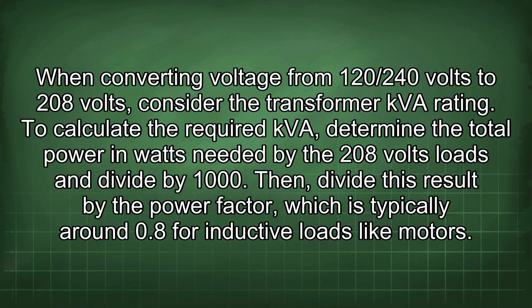When converting voltage from 120/240 volts to 208 volts, consider the transformer kVA rating. To calculate the required kVA, determine the total power in watts needed by the 208 volt loads and divide by 1000. Then, divide this result by the power factor, which is typically around 0.8 for inductive loads like motors.